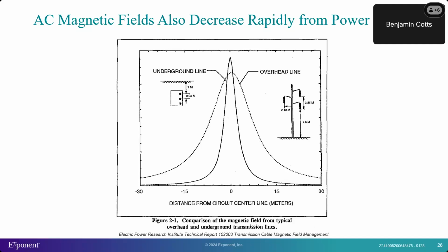But this also shows that as you move away in distance, while the magnetic field from the overhead line decreases quickly with distance, the field levels from the underground line decrease even more quickly. This is essentially because the three conductors of the underground transmission line are closer together, and the magnetic field created by each of the three conductors cancels out somewhat the field from the other two. So the closer you can bring those conductors together, the lower the field levels will be, and the more quickly the fields will drop off with distance.